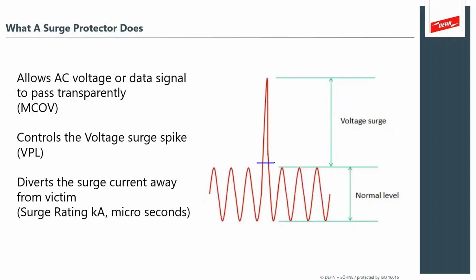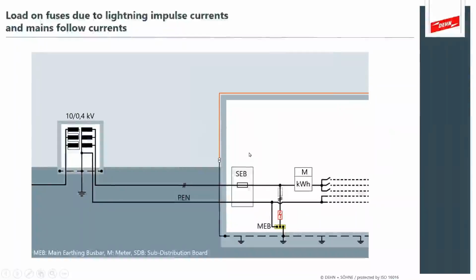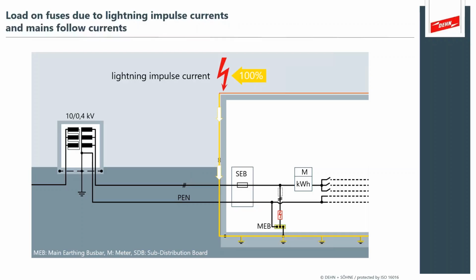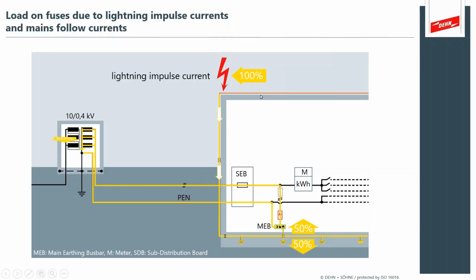A surge protector is not the same as a high voltage arrester out at a 100 kV line. Those products exist and they're important. Those are arresters. Surge protection is described as below 1,000 volts, 1,500 volts for DC photovoltaic. Okay, so we want to chop that bit off the top. So what's the surge look like? Well, one description is it comes down the down conductor and induces voltage, and half of the current diverts into the earth and the rest actually induces into the rest of your building.